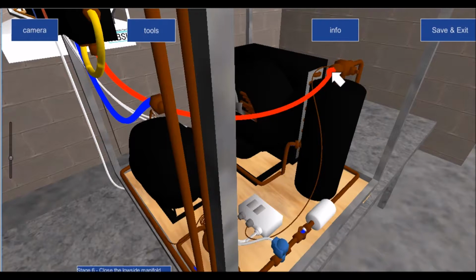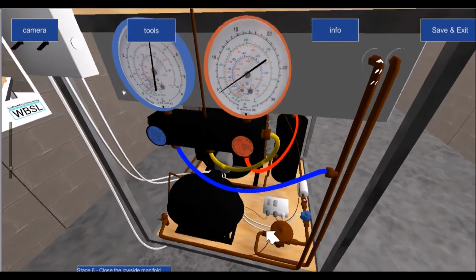So as soon as we loosen the hose line, we have to be able to close it when we think that we've finished purging air and we've now just got refrigerant, and it only needs to be a short, sharp purge as opposed to a big long purge. Because again, this is why I'm coming back to harp on about a last resort. We do not want to fit gauges on as a first resort. We want to get into the habit of fitting gauges as a last resort. And if we can get away with diagnosing and fixing the system without fitting any gauges, that's all the better. So we try our best not to fit gauges.